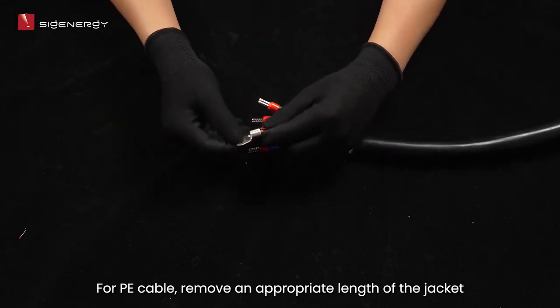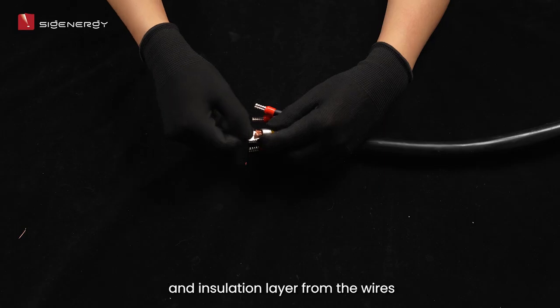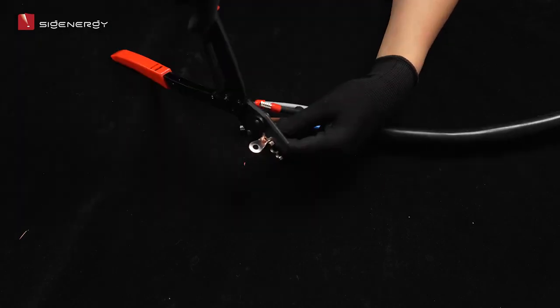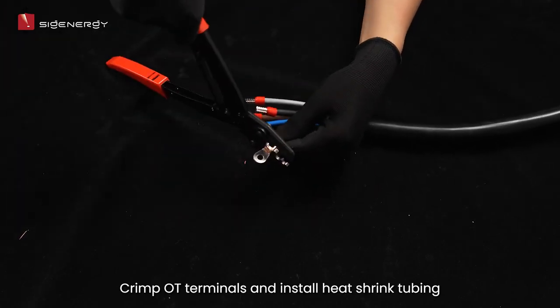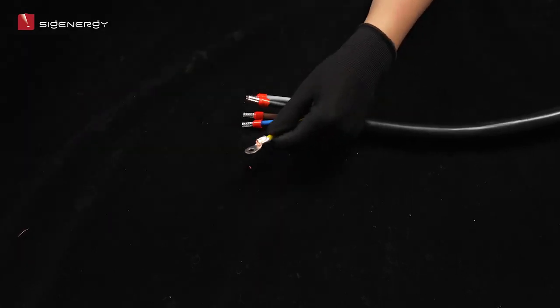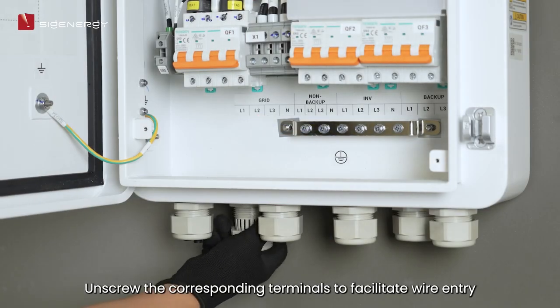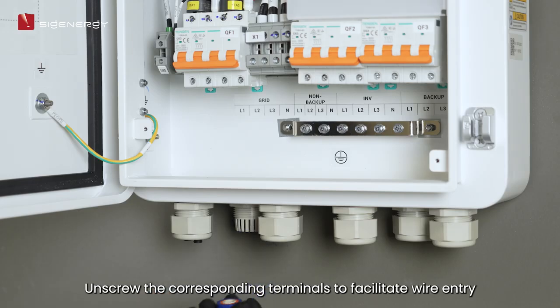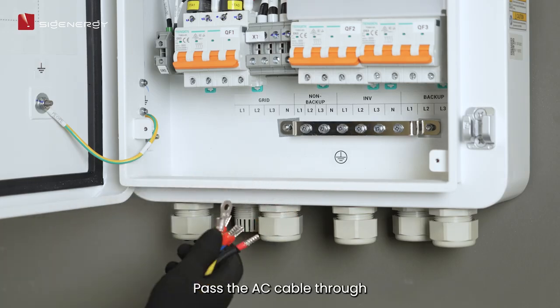For the PE cable, remove an appropriate length of the jacket and insulation layer from the wires. Crimp OT terminals and install heat shrink tubing. Unscrew the corresponding terminals to facilitate wire entry. Pass the AC cable through.